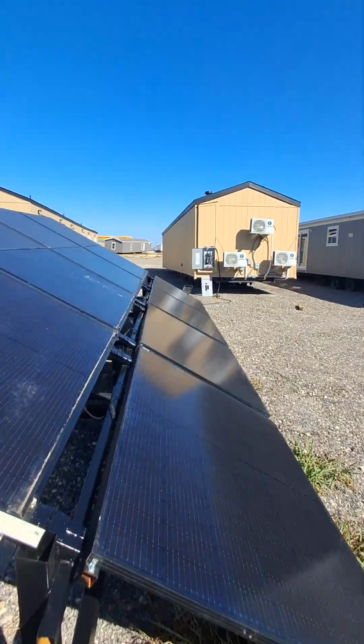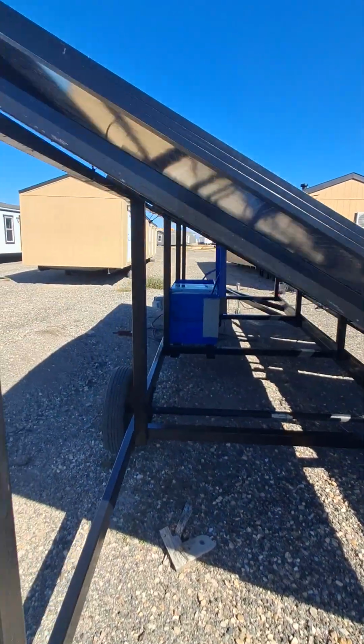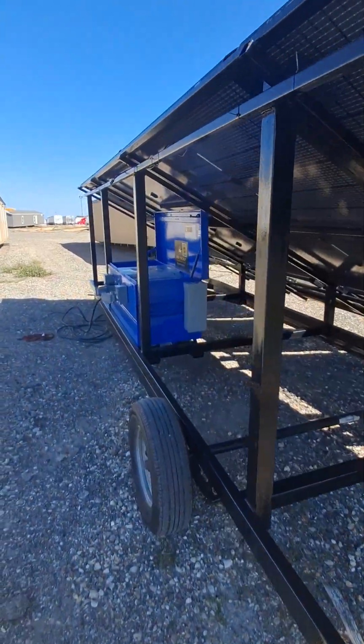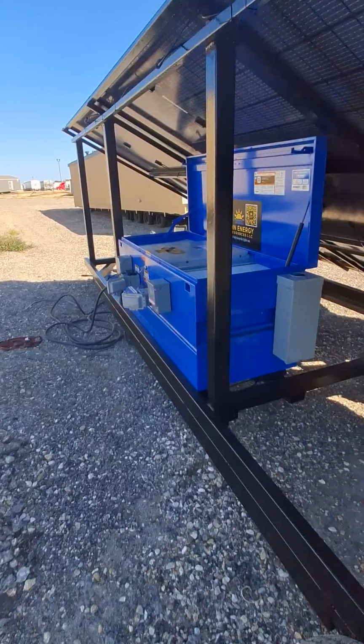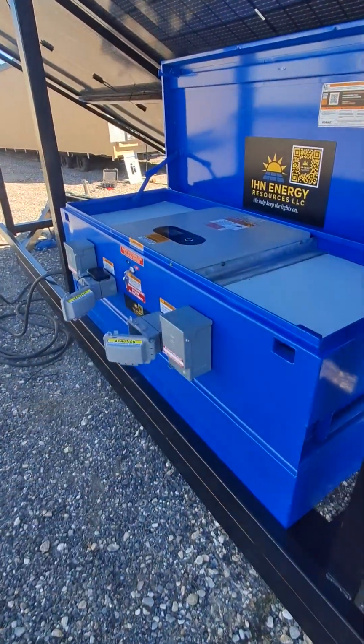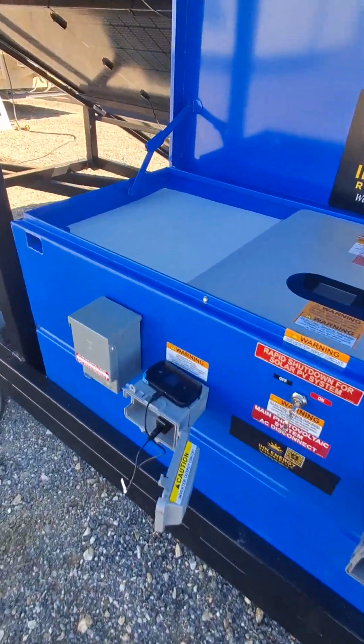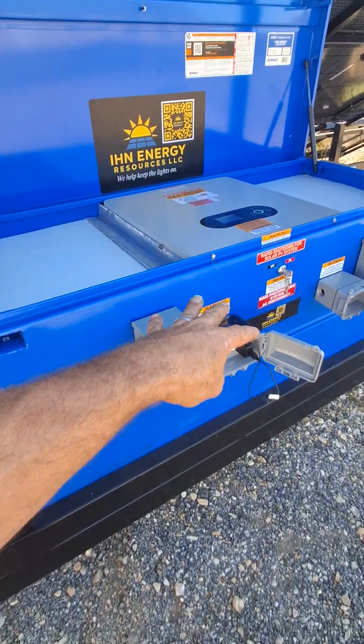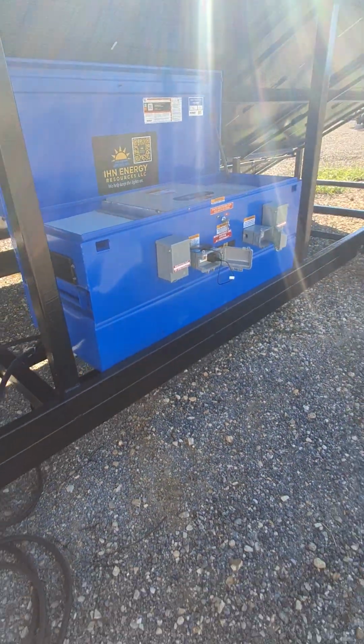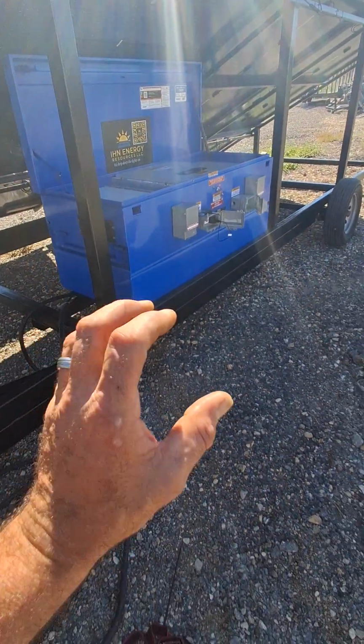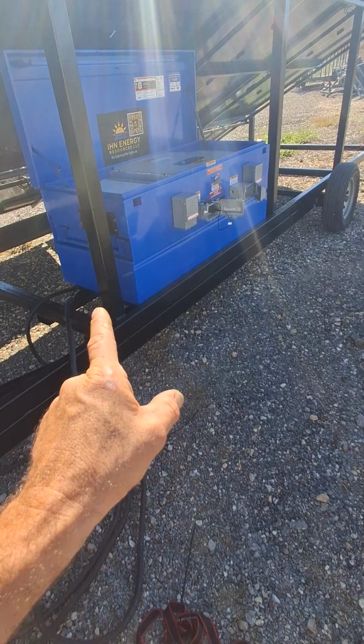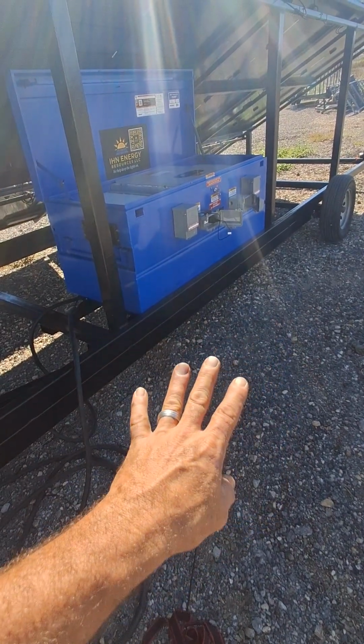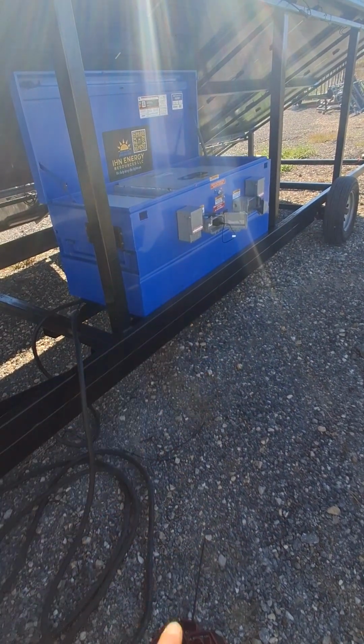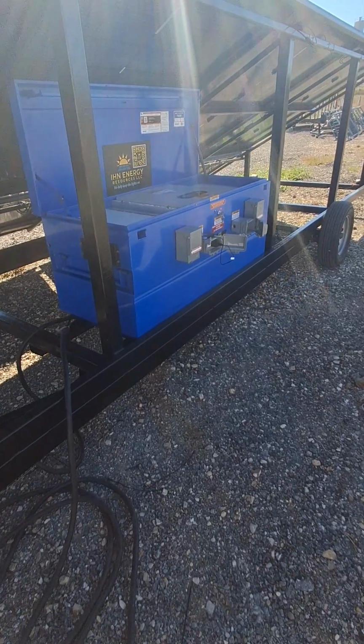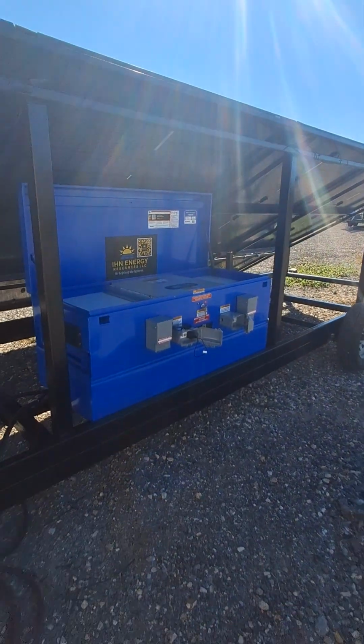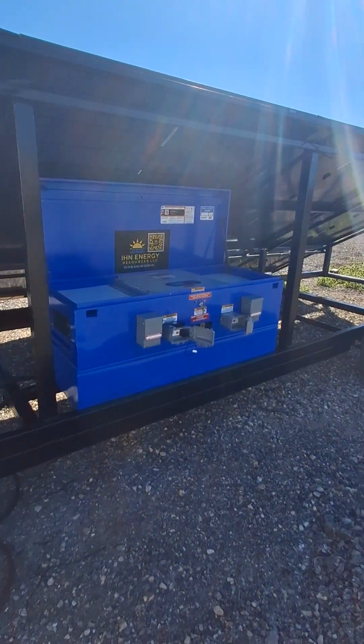What this system needs is what's on this battery bank. I have 60 kWh of storage capacity, lithium iron phosphate, 51.25 volts, built into a 16 cell configuration. That means it takes 16 of these individual batteries in configuration with a BMS, battery management system, to equal one battery. There's 4 of them, so a grand total of 64 battery cells inside this bank running off of 4 JK BMS systems.